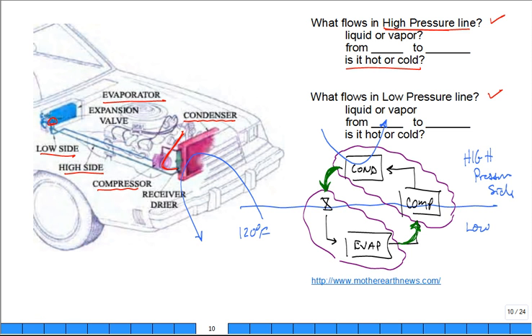So what's the temperature of the refrigerant in the condenser? A good 15-20 degrees higher. Does that make sense? The refrigerant in here is, let's say, 145 degrees. It comes out liquid. I know it comes out liquid out the condenser. But if I touch that liquid line, if I touch that high pressure liquid line right here, it's hot. High pressure liquid, hot, going from the condenser to the expansion valve.